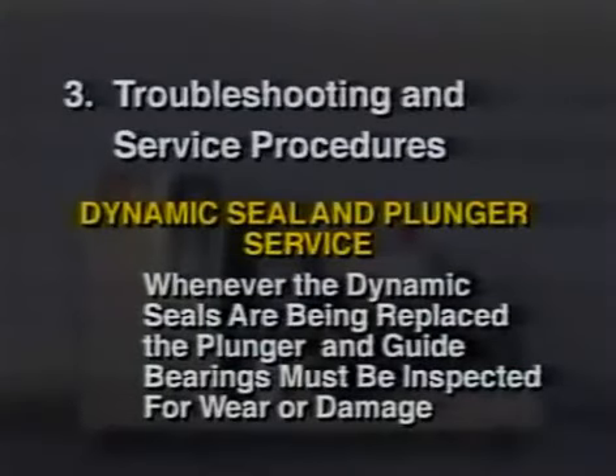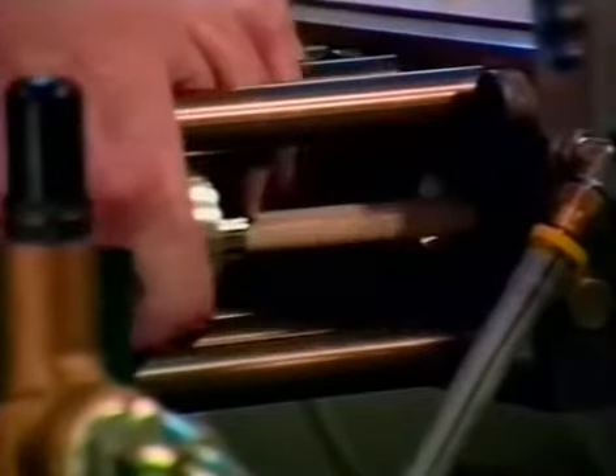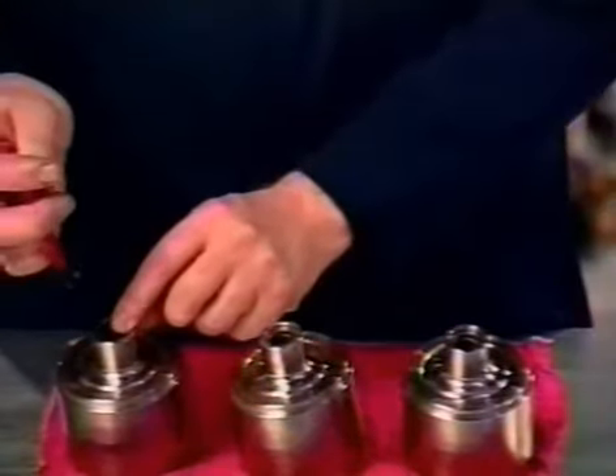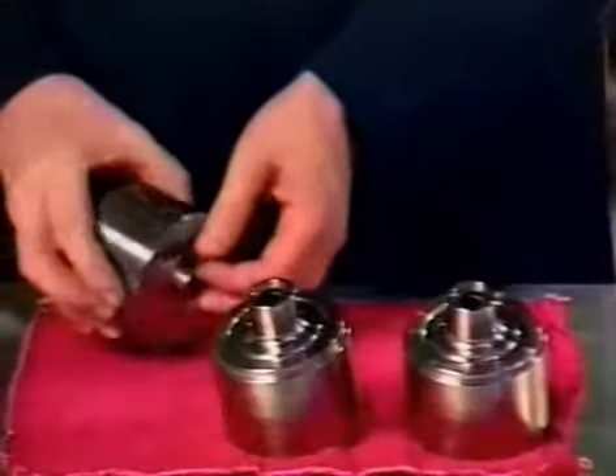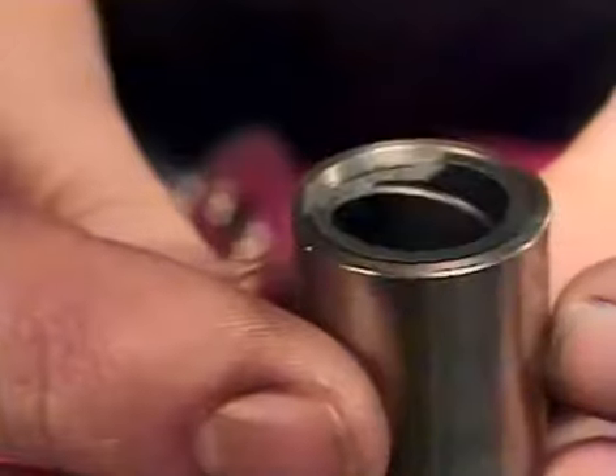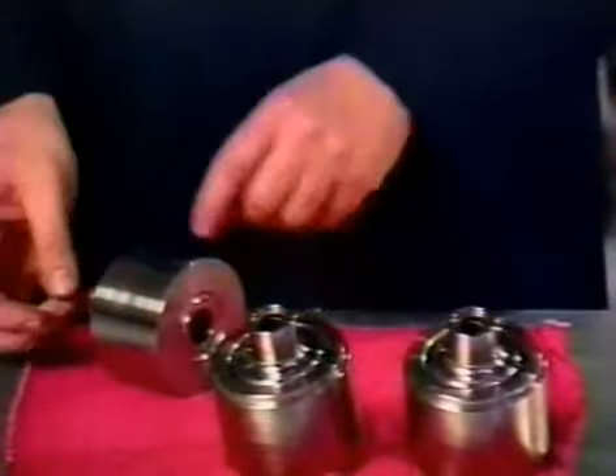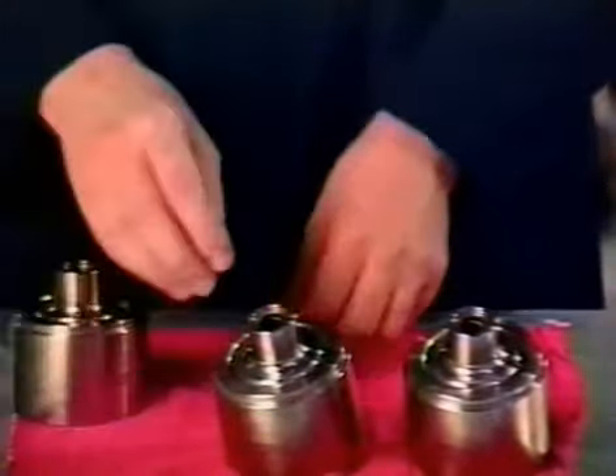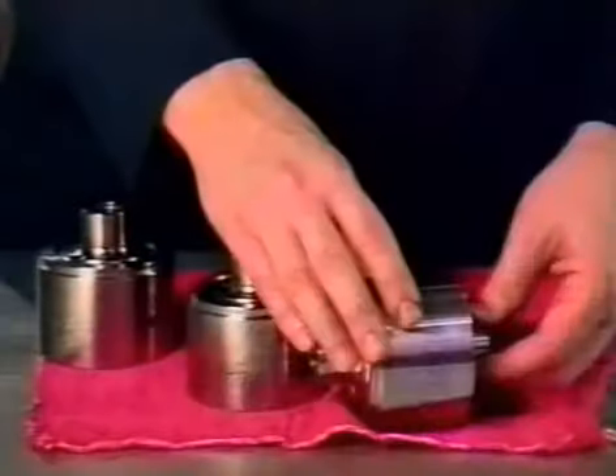Whenever the dynamic seals are being replaced, the plunger and guide bearings must be inspected for wear or damage. Slide the bearing carrier off the plunger. Remove the snap ring that retains the forward guide bearing. Remove and inspect both guide bearings. Replace the guide bearings if you see evidence of chipping on the inside diameter. Slide the guide bearings onto the plunger, and if there is excess play, replace the guide bearings. Another sign that the bearings are worn is if the backup ring shows signs of plunger rubbing.